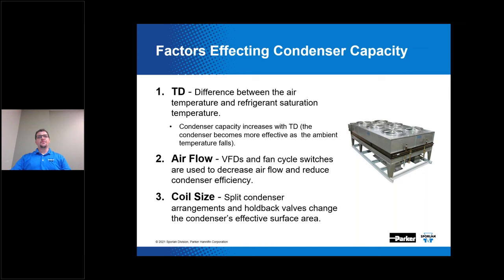Factor number two is airflow — VFDs and fan cycle switches are used to decrease airflow and reduce the condenser efficiency. Your third factor is coil size, and you directly impact the coil size when you use split condenser arrangements and condenser hold back valves that change the condenser's effective surface area. As your ambient temperature falls, less heat may need to be rejected, but the increased TD allows the condenser to reject more heat, causing a drop in your high side pressure. As that pressure continues to fall, further actions can be needed to prevent it from reaching unacceptable levels that would impact system performance negatively.